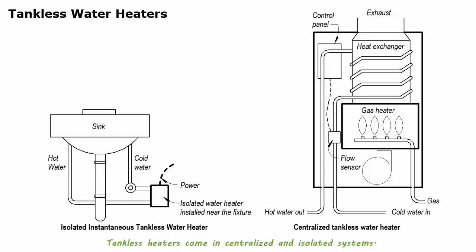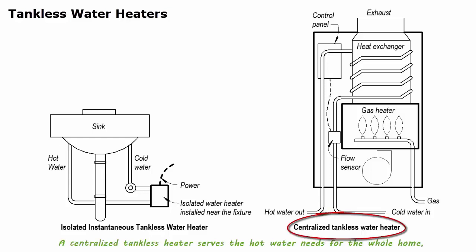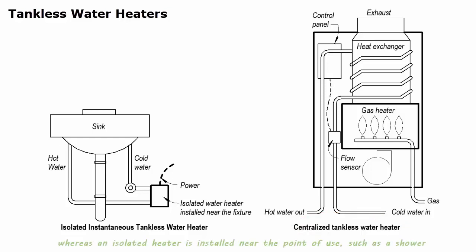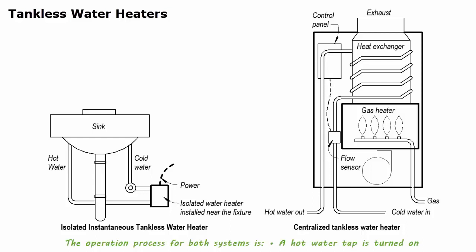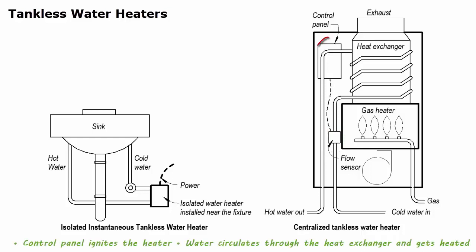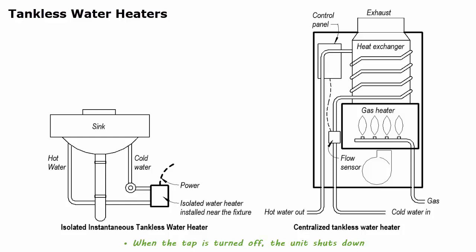Tankless heaters come in centralized and isolated systems. A centralized tankless heater serves the hot water needs for the whole home, whereas an isolated heater is installed near the point of use, such as a shower or bathroom sink, so users can have instant hot water. The operation process for both systems: a hot water tap is turned on, water flows into the heater, a water flow sensor detects the flow, the control panel ignites the heater, water circulates through the heat exchanger and gets heated. When the tap is turned off, the unit shuts down.